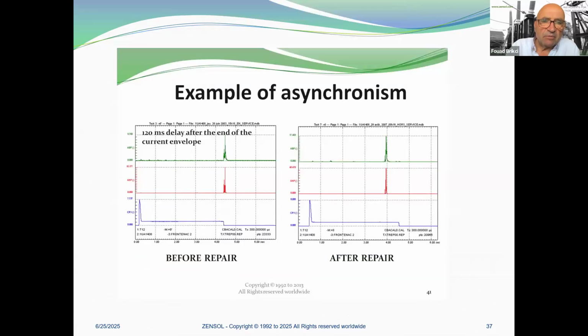Here it's also a simple problem to be detected quickly. It's an example of asynchronism. Here you see the diverter switch, which in normal condition, the switching operation should occur before the current stops flowing in the motor. In the case illustrated on the left, the switching operation signal is delayed by 120 milliseconds after the end of the current envelope. As can be easily observed, this kind of issue doesn't require the use of a reference signature, and the asynchronism can be detected immediately.